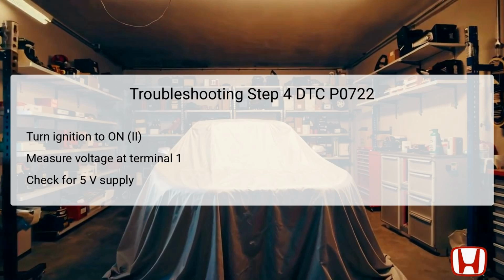If you find that this voltage is present, it confirms that there is no issue with the power supply to the sensor, and you can proceed to the next troubleshooting step. Conversely, if the reading is absent, it indicates an open circuit that needs addressing before moving forward in the diagnostic process.